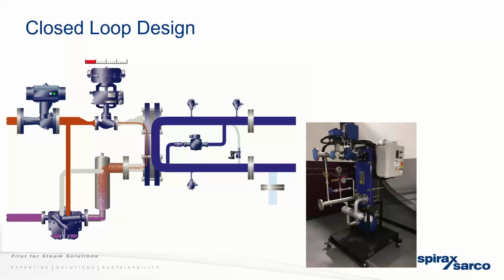To the process. So the process could be your wash down hoses. So now they're just water hoses. They're not a mixing hose. There's a number of safety features on here. If the temperature senses the water is too hot, there'll be a tempering valve here. So some of the cold water will bypass the heat exchanger and cool down the water that has come out too hot. So if for some reason there was a quick change in process and a spike in water temperature, this valve will open to temper that water and bring it back down to the set temperature.